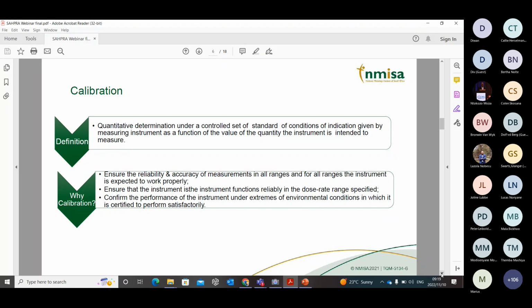Okay, then also in my first slide, I mentioned the word calibration. Then we ask ourselves, what is calibration? Calibration is a quantitative determination, under a controlled set of standard conditions, of the indication given by the measuring instrument as a function of the value of the quantity the instrument is intended to measure. So in simple terms, we can say calibration is the comparison of the unknown to a known with an associated uncertainty. When we say the known, we are referring to the national standards kept and maintained at the National Metrology Institute of South Africa.